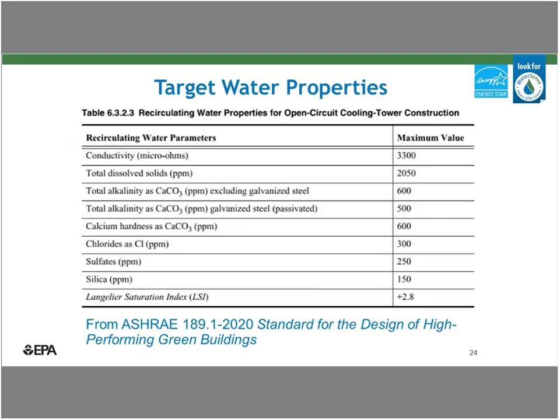I just mentioned that you should try to identify a target cycles of concentration that is achievable based on your facility's incoming water quality. This table is from ASHRAE 189.1, which is the standard for the design of high-performing green buildings. ASHRAE establishes maximum values for certain parameters that recirculating cooling water should stay below. This information can be very helpful as you identify your cycles of concentration limit. So for example, if your limiting parameter is total dissolved solids, or TDS, you can identify your target cycles by evaluating incoming water quality.